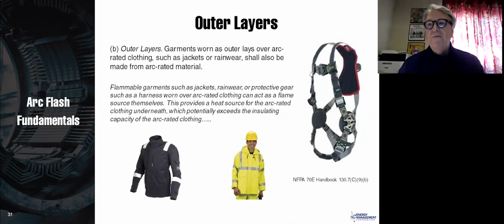Do you need to have, if you're going to go up and you're going to wear something like a harness, let's say, does that harness need to be arc flash rated? And the answer is yes, it does. If you have raincoats, if you have harnesses, if you have anything that you wear over your PPE, they need to be arc flash rated, because that arc flash gear is meant to protect you from an arc flash explosion. But if something over you is on fire and literally burning, then none of that arc flash gear is meant to protect you from third-degree burns due to things that you're wearing that are on fire. So anything that you wear over your arc flash gear must be arc flash rated. And those raincoats, harnesses, those types of things, they're readily available in an arc flash rating.